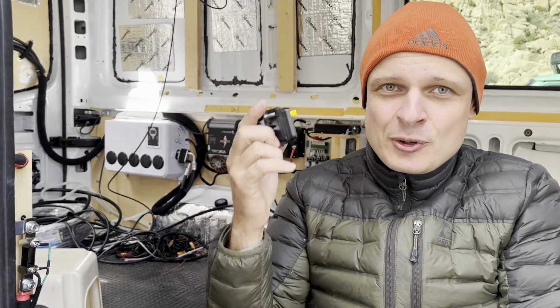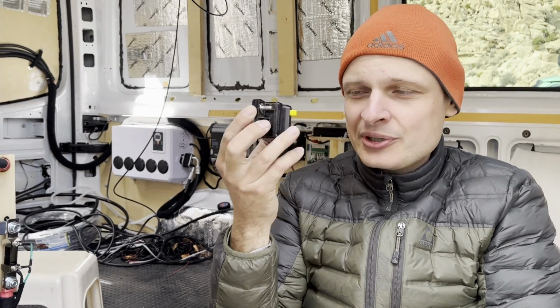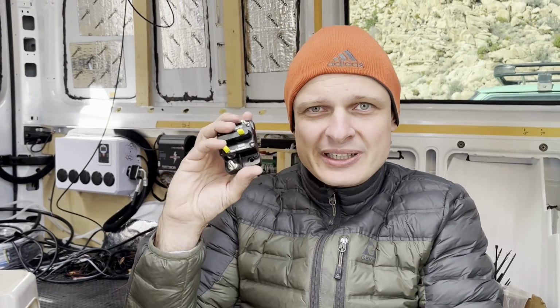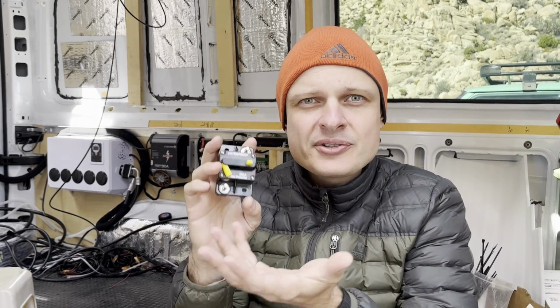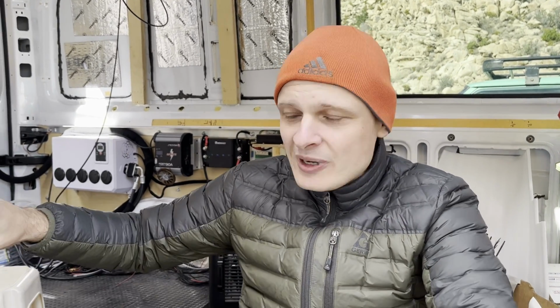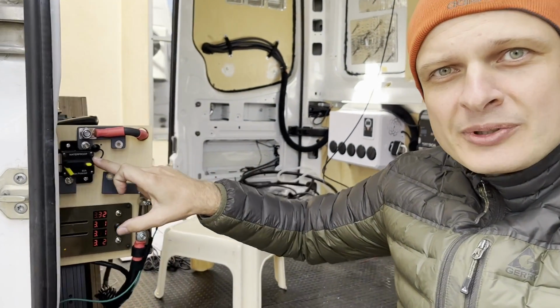So if I put a 300 amp fuse or circuit breaker on my circuit and it pops too early, okay, that's annoying, but not a big deal unless it's a critical thing. Even this one, it pops at 192 amps, close enough to 200. Maybe it's okay. But this one is an 80 amp circuit breaker.